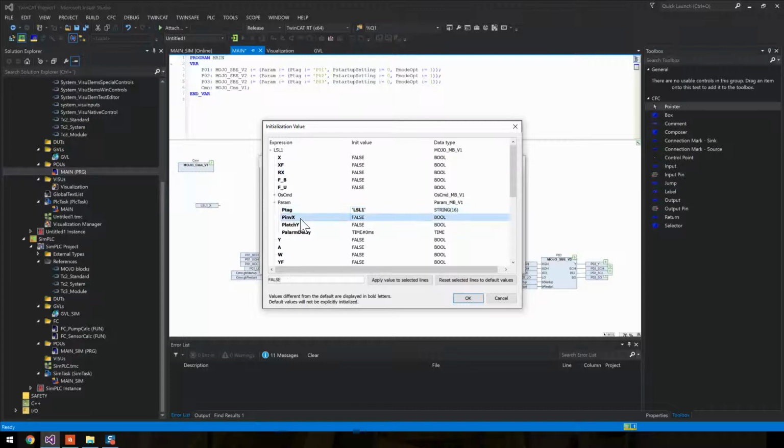And here we can invert it. We can invert it outside as well. So in this case, let's do it inside. Latch. Would like to keep it true if it has been true. So you actually have to manually confirm for it to go off again. And I'd like it to not give an alarm before it's gone past, let's say, 100 milliseconds.